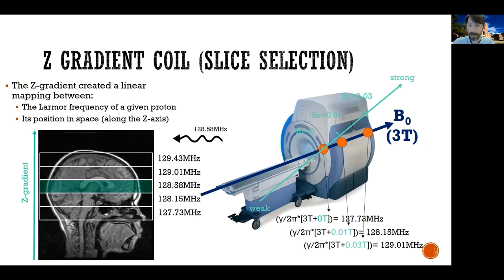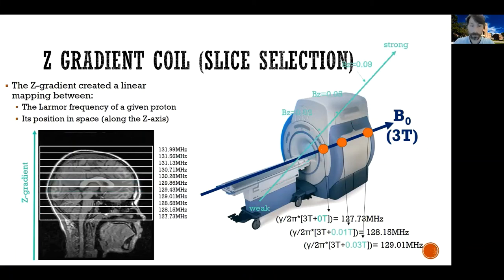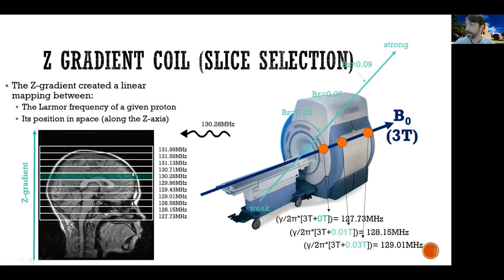If I make the gradient steeper, I can divide the head into even smaller slices. A radio frequency pulse at 127.73 would only excite a tiny slice down here, and a pulse at, say, 130.28 megahertz would excite only protons in a different slice. That's why we call this the slice selection gradient — it allows me to push into the transversal plane only protons inside one selected slice. When I receive the signal back, I'm only receiving signal from protons in that slice.